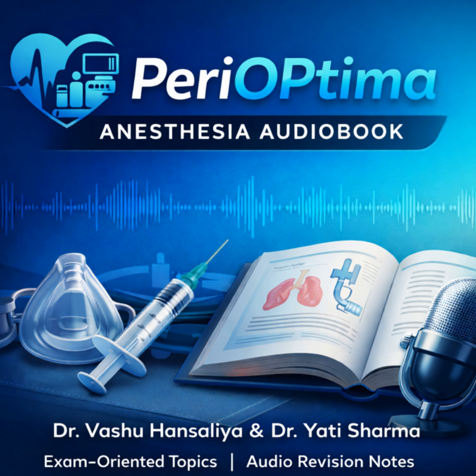Okay, let's make this practical. Let's take VOO mode. Good, let's break it down. VOO, paced, ventricle sensed, none. Response to sensing, none. So it's just firing blindly into the ventricle. Exactly. It is asynchronous. It will pace the ventricle at a fixed rate, say 70 beats per minute, regardless of what the patient's own heart is doing. It ignores the intrinsic rhythm. That sounds dangerous. Couldn't it fire on a T wave? It absolutely can. In a conscious patient with an underlying rhythm, you risk the R-on-T phenomenon, which can trigger ventricular fibrillation. However, there's a time and a place for it.